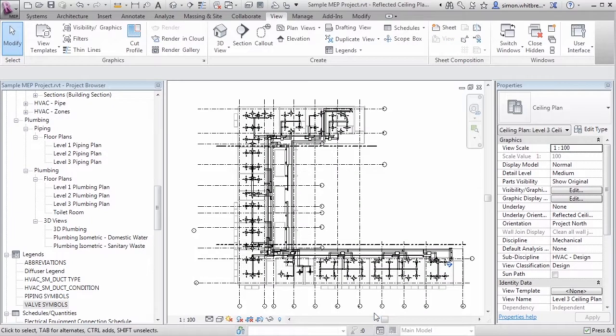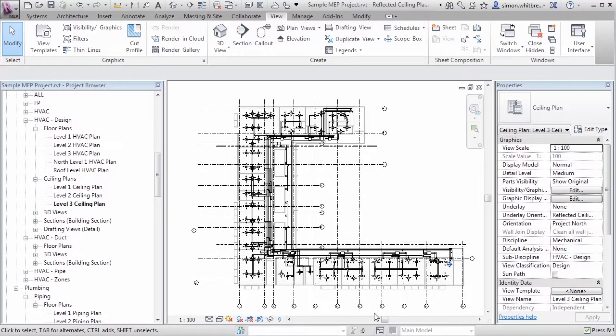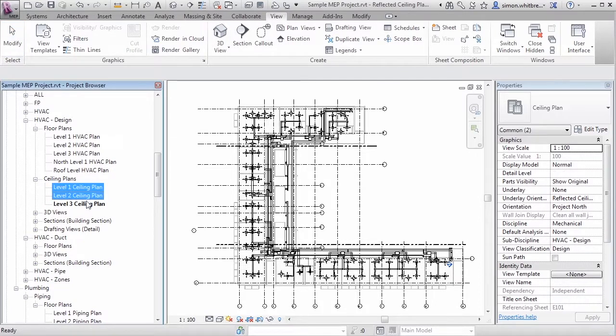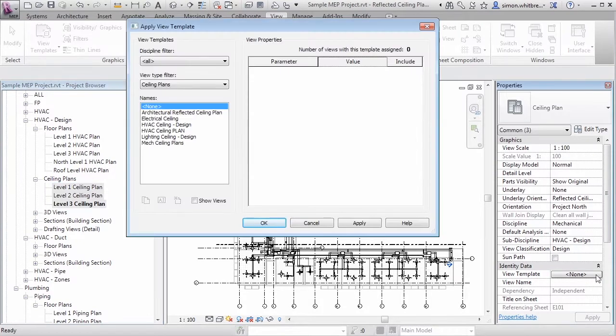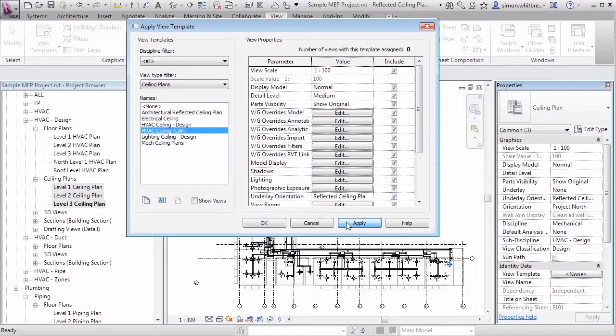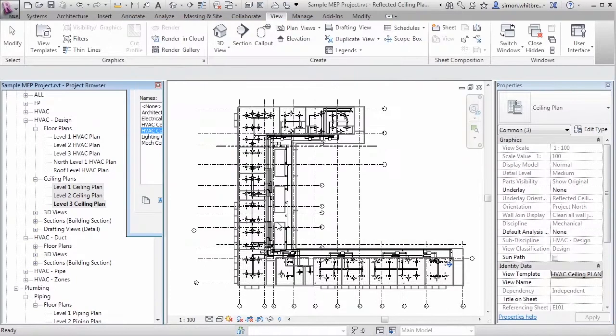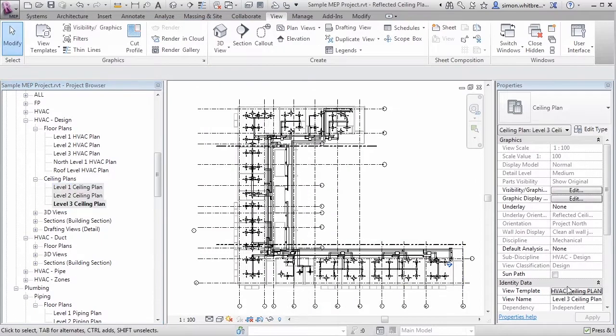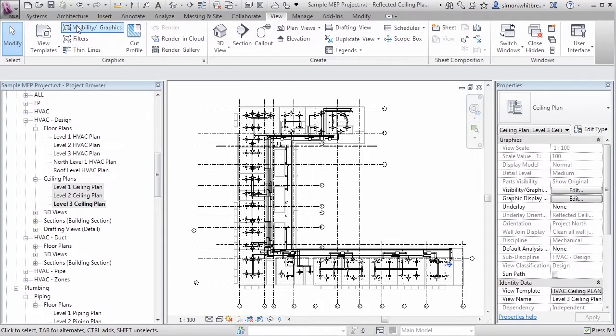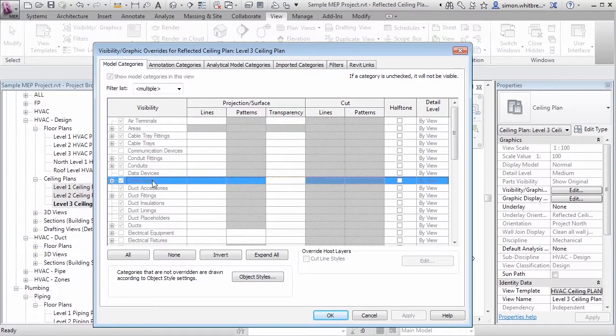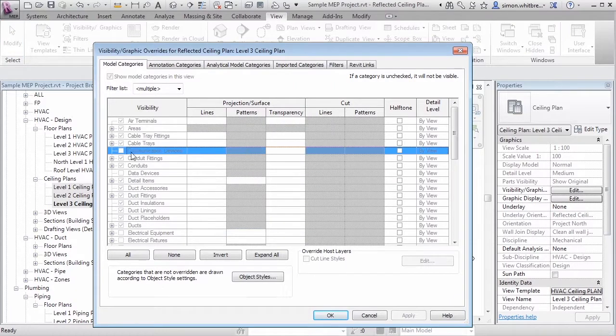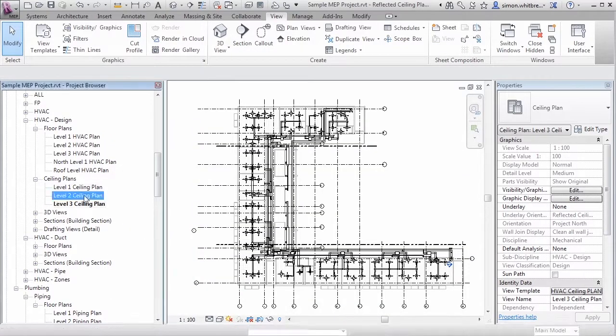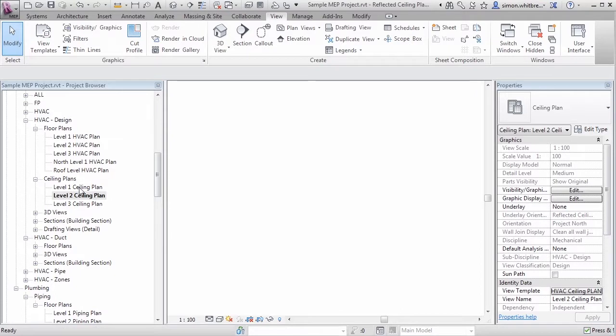If however I want all my ceiling plans to be identical I can now select those three ceiling plans and from the Properties palette select a view template from here. If I select the HVAC Ceiling Plan this time I get to Apply this and click on OK. This now shows that we have a view template associated with each view. And if I go to the Visibility Graphics dialog box you can see that I'm now no longer able to individually change these elements. And all three views are identical.